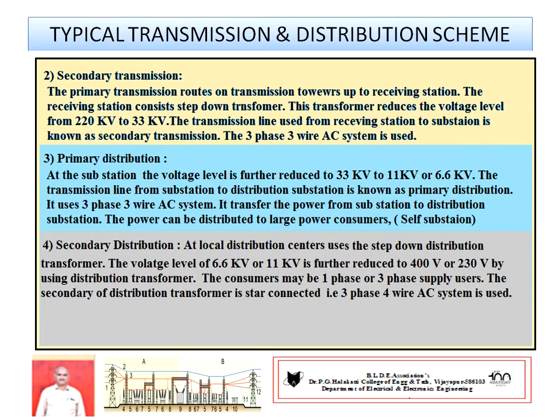Number three: primary distribution. These are transmission lines from the substation to the distribution station. The voltage level is further reduced from 33 kV to 11 kV or 6.6 kV. If large industries have their own switchgear, supply may be permitted directly from the primary distribution level to large power consumers.